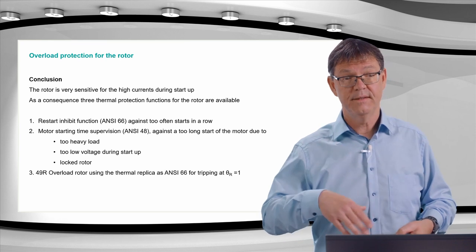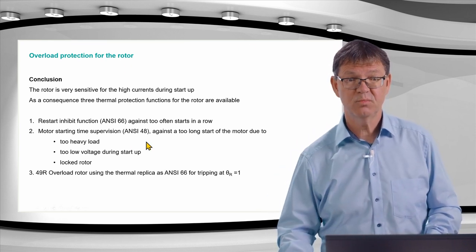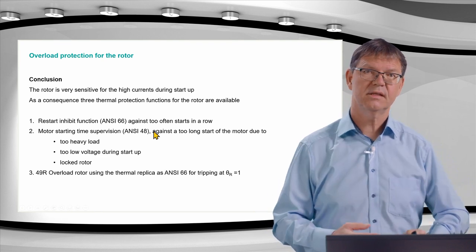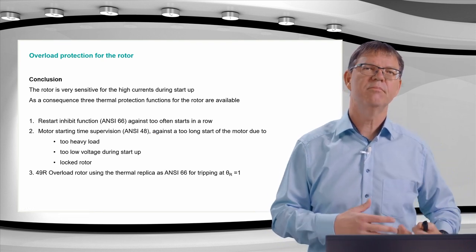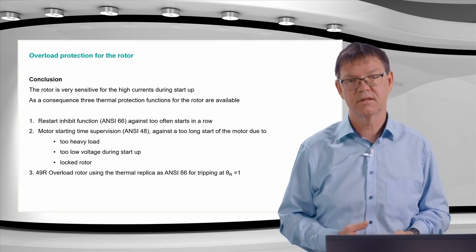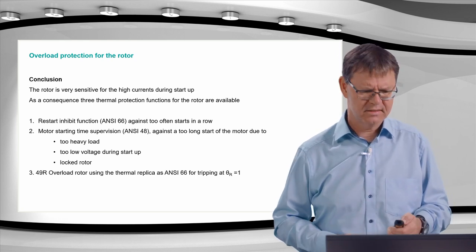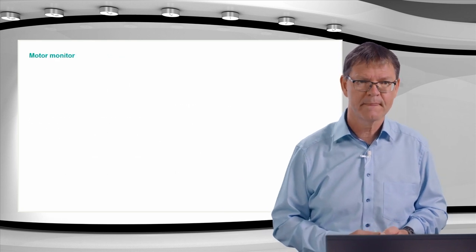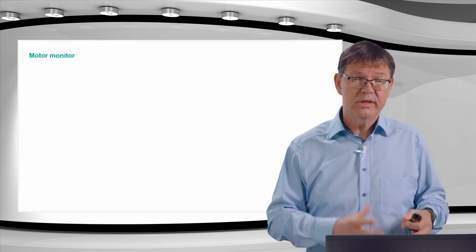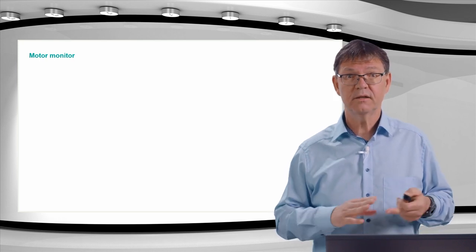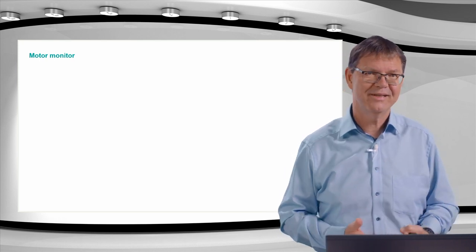Whereas the motor starting time supervision, as a difference, works for one start, and here we define the maximum time we can use for the starting up of a single start. Of course, these depend on each other, so there are some relationships between them. Okay, before we go into the detail of the restart inhibit function, first some preparation, let's call it like that.